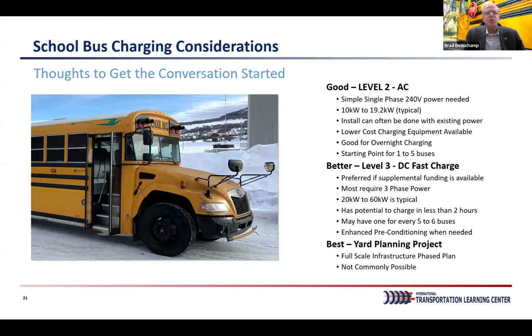So a good, better, best strategy in starting out. Obviously, if you're getting a wave of buses and it's 1 to 5, the starting point could be simple, single phase power, 240 volt AC charging. That ranges from manufacturers that are 10 kilowatt all the way up to 19.2 kilowatt, typically a 48 amp to 80 amp single phase 240 volt circuit. Installation can often be done in your yard with existing power, often available in a convenient spot where buses already park. It's low cost to get started, and good for overnight charging scenarios.